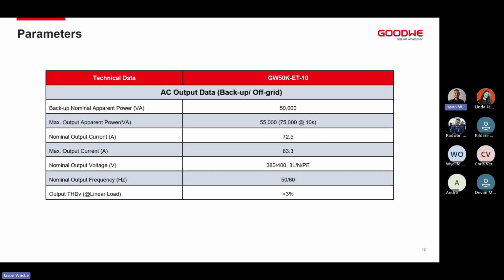What's very nice about this, like I mentioned, it does get done through the DC capacitor bank inside the inverter, meaning that we don't have any additional pull or any additional power requirement from the battery, which means we're not going to try and damage the battery in any way. We're not going to try and pull any additional power from the battery or anything like that. Battery is capped to a limit of 100 amps, 55 kilowatt discharge, which means if there is any additional power that needs to come out of the system, it gets done through the DC capacitor bank in the inverter.